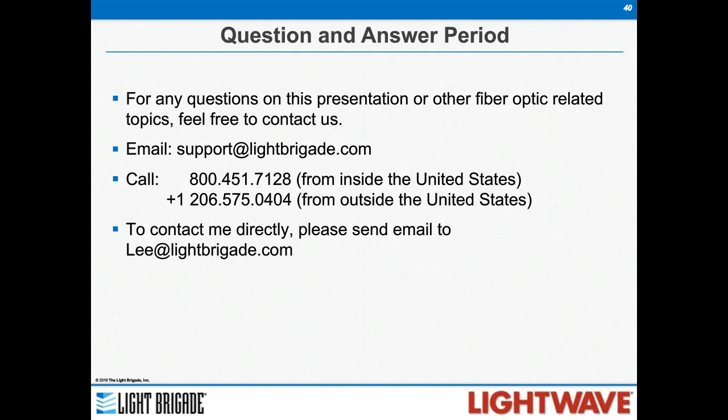So there's a question on single mode loss testing for one jumper method. How is the loss of the test reference cord number 2 obtained since it's not included in referencing? Or is test reference cord number 2 considered minimal and therefore omitted? So yes, the second part of that.